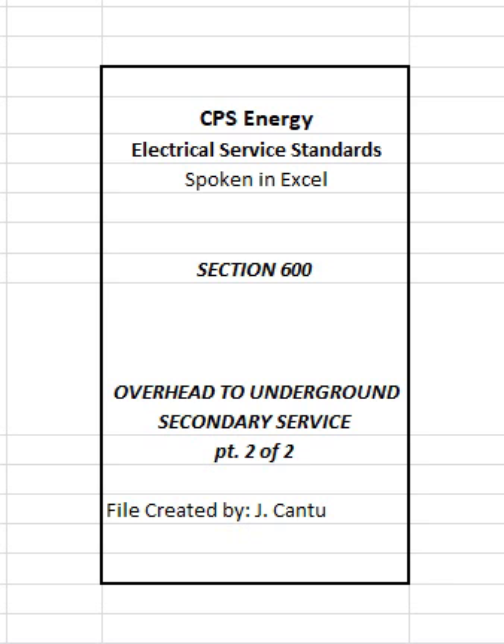C. Step bus auxiliary gutter. Directly to bus within customer furnished and installed step bus auxiliary gutter meeting CPS Energy standards and specifications. Step bus auxiliary gutter shall be provided with lockable and sealable means for use by CPS Energy where installed ahead of CPS Energy metering equipment. Note: step bus auxiliary gutter is required any time service lateral conductors, or any one set of service entrance conductors exceeds single 500 kcmil conductors or parallel 350 kcmil conductors.